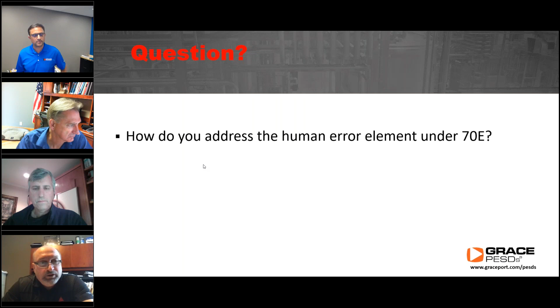The supervisor really has to have a good rapport and relationship with their workers, meet with them in the morning, talk with them on the phone, and have some gauge if you can, but it's not perfect. At the end of the day, the employer tries to manage the worker in real time before they do an actual energized electrical work task, because the risk assessed procedure would have one consideration being whether the worker is fit to do the work mentally and physically. I recommend the employer have documentation in place where right before the worker proceeds to do the energized work, the worker acknowledges they are of good state of physical health and mind, and signs off on it. This is in the field where the supervisor isn't there. It's a loaded question, there's more to it than simply saying you can't manage it, but the employer can with some of what I just suggested.